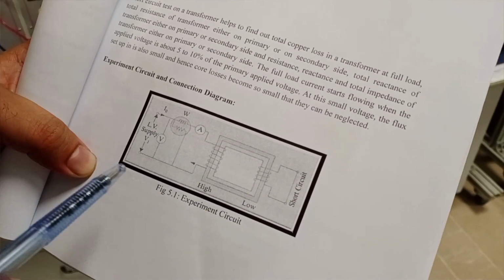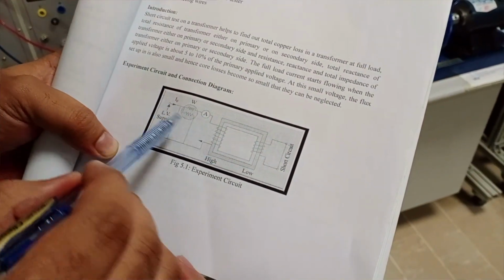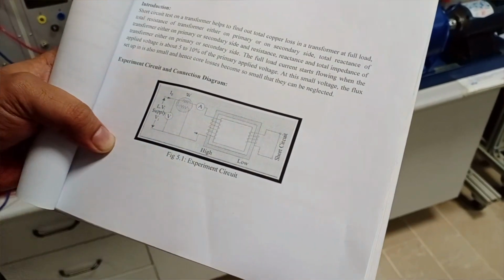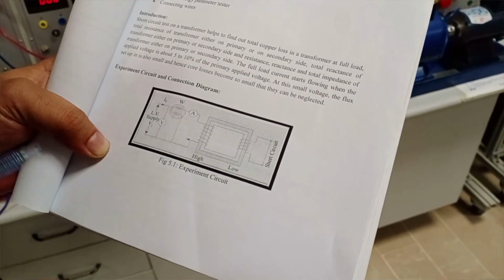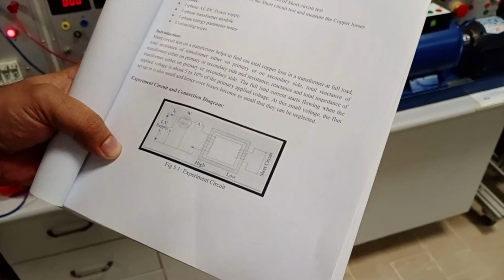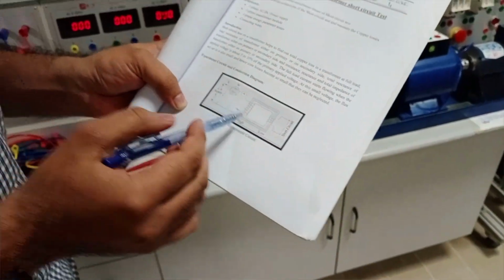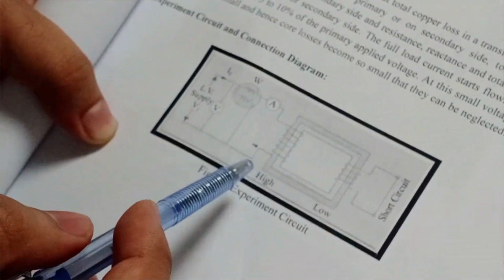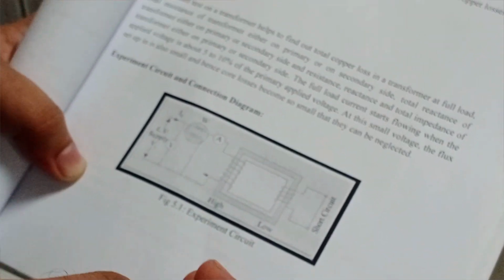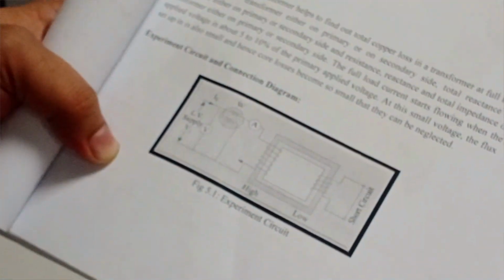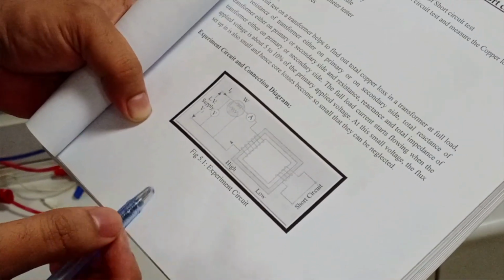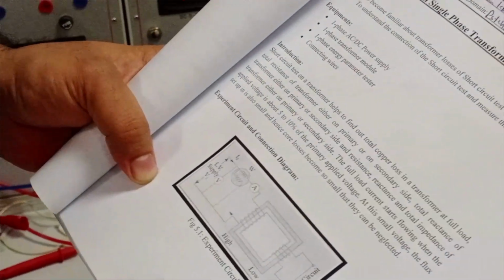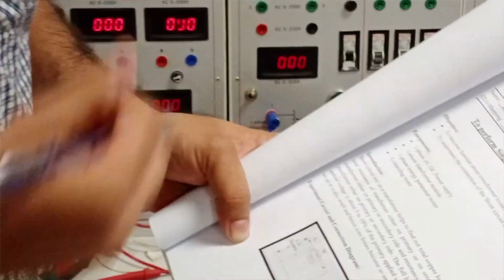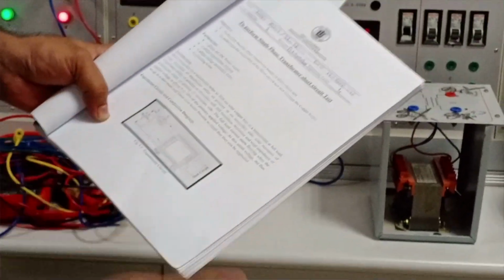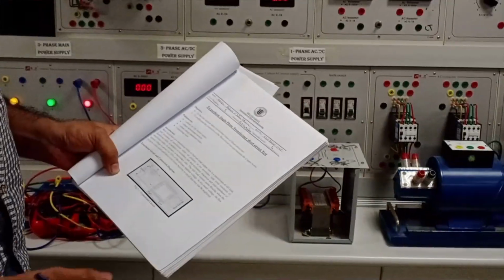Now, if you apply a very small amount of voltage to this circuit, 5 to 10% of the rated voltage, if our high voltage side is up to 100 volts, the full load current will start flowing through the transformer. That shows our copper losses. Okay, now we have to conduct this experiment on the trainer.